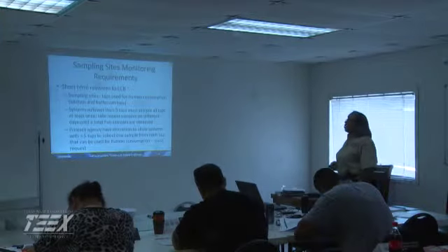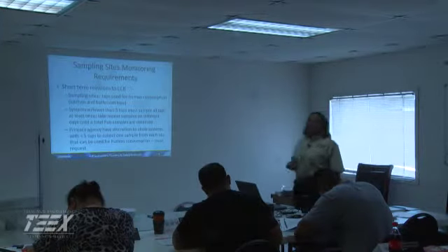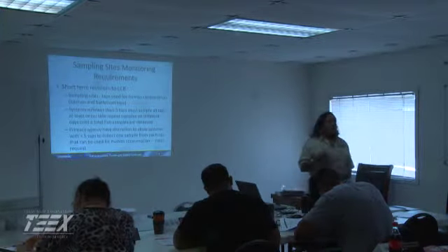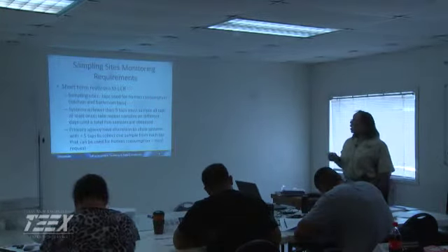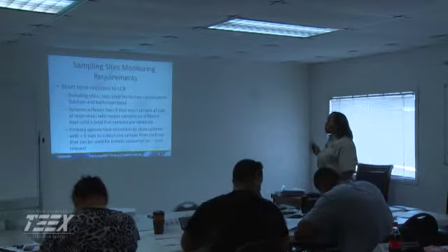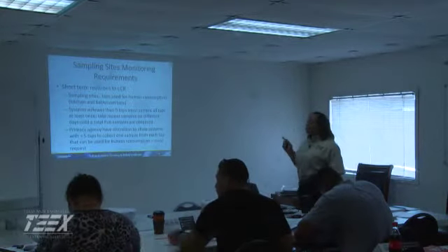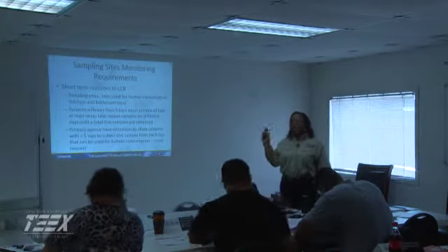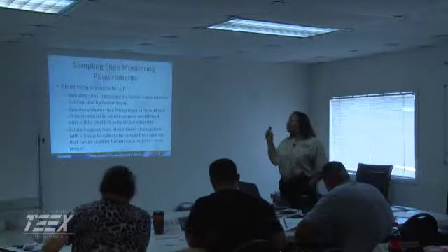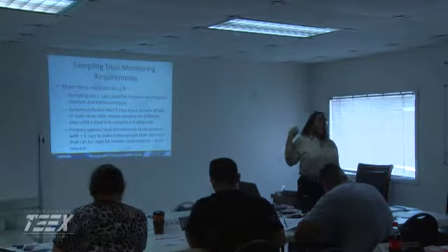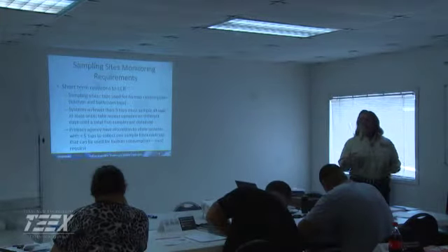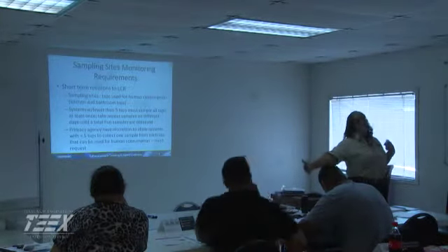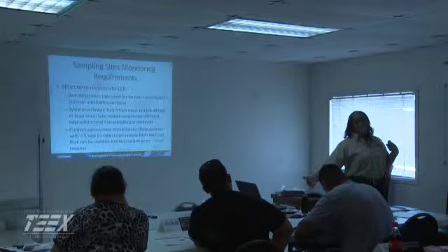All right, now the short-term revision, again, 2007 is when you had some revisions to the lead and copper rule. One of the main things was that the taps you sample from must be taps that are used for human consumption. That's critical. And usually that refers to kitchen or bathroom sinks or taps. In other words, I can't go outside the house and pull a lead and copper sample.